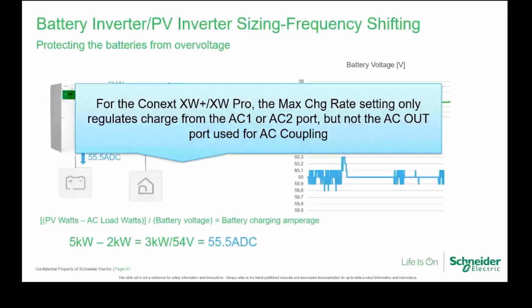Now for the Conext XW Plus and XW Pro, the maximum charge rate setting only regulates charge from the AC1 or AC2 port, but not the AC output port for AC coupling. That means don't rely on the maximum charge rate, because it doesn't apply when you're charging from the load side. That's why it requires the frequency shift to work correctly, so you don't overcharge your batteries.